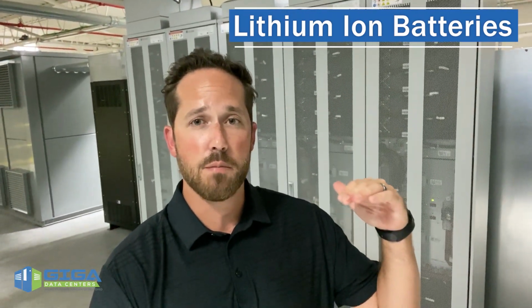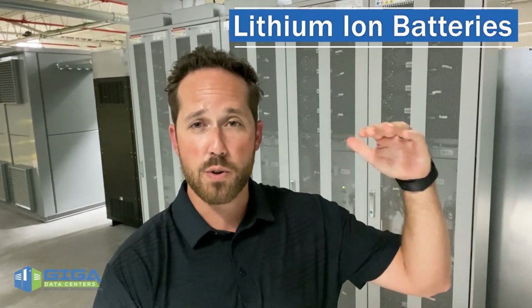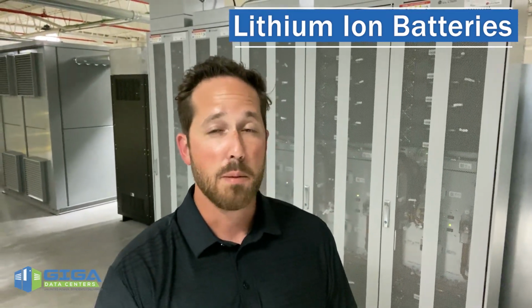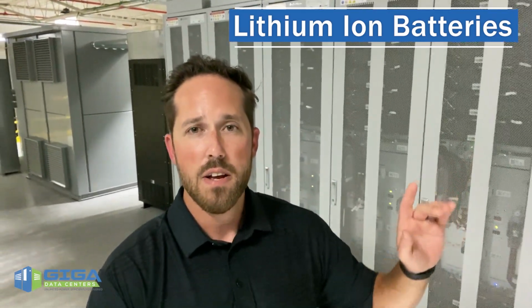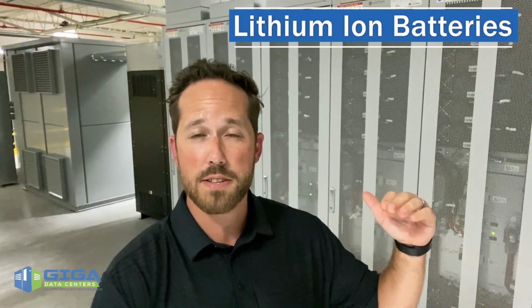The composition we use is lithium iron phosphate, because these can reach much higher temperatures before any thermal runaway could occur, about 270 degrees. Each rack behind me supports 200 kilowatts of lithium-ion batteries, which are also hot swappable.